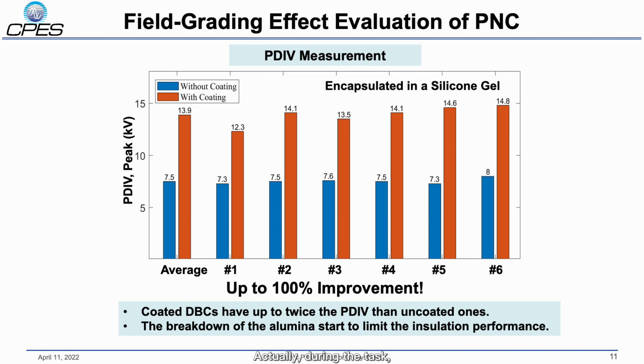And actually, during the test, we started to see some breakdown inside the alumina before the encapsulation failure, which means the alumina starts to limit the insulation performance instead of the silicone gel, which is usually the bottleneck of the insulation for medium voltage power modules.